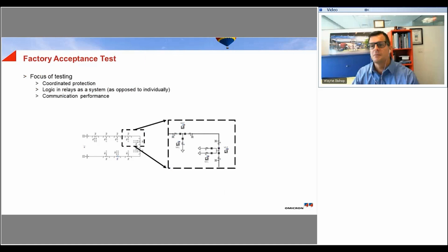Based on, I think, a 2017 NERC study, while each relay as a component would have been thoroughly tested, very often the interface between components is the cause of most misoperations. So in this system test, errors in communication engineering could not be uncovered with any kind of single relay testing because of the communication between the different relays and their response being necessary. Therefore, to lower the complexity and improve their test coverage, we implemented this new system-based approach.